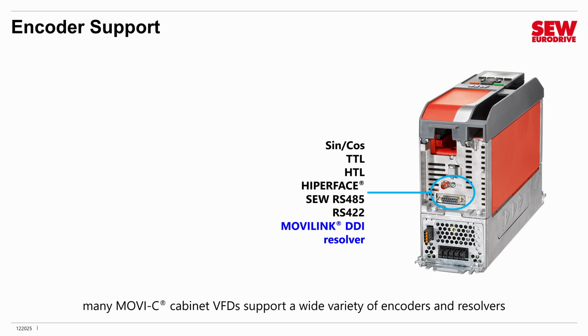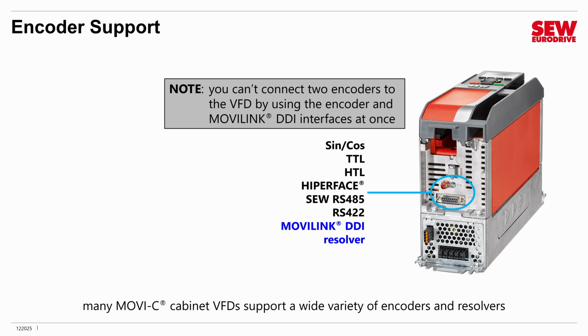People often ask me in my classes, if I need two encoders, can I connect one to the MOVI-Link DDI and the other to the encoder interface? And I have to reluctantly tell them, no, you can't do that. When you activate the encoder interface, it shuts off MOVI-Link DDI, and when you activate MOVI-Link DDI, it shuts off the encoder interface. So you can only use one at a time.